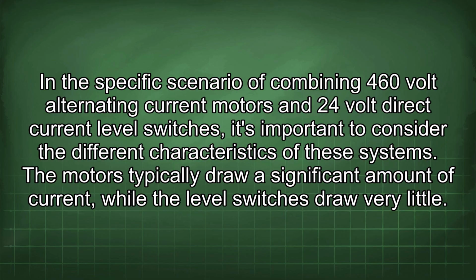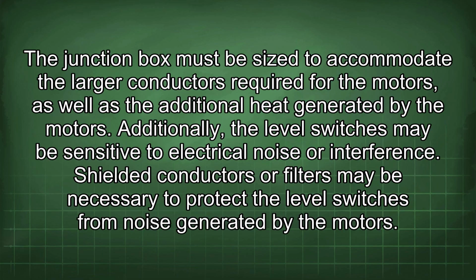In the specific scenario of combining 460-volt alternating current motors and 24-volt direct current level switches, it's important to consider the different characteristics of these systems. The motors typically draw a significant amount of current, while the level switches draw very little. The junction box must be sized to accommodate the larger conductors required for the motors, as well as the additional heat generated by the motors. Additionally, the level switches may be sensitive to electrical noise or interference. Shielded conductors or filters may be necessary to protect the level switches from noise generated by the motors.